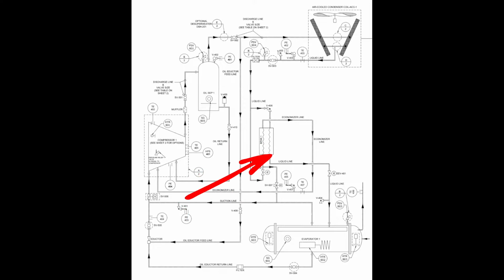So keep in mind that the saturation temperature on this braze plate is not at suction pressure. Suction or evaporator saturation, right? This actually runs a higher saturation because that's all we need it to do, right? We're not trying to get 45-degree saturations for our liquid line. I think the manual said it's trying to achieve 1.2 times the evaporator saturation as kind of its ballpark set point. So if you're running a 45 degree, multiply that by 1.2 or so, and you would expect the economizer intermediate pressure or intermediate saturation to be in about that range. And then we're coming into, I think it was, 1.67 times suction.